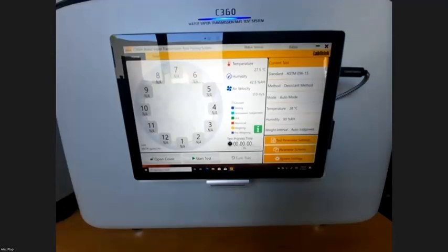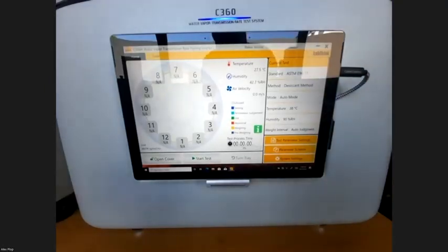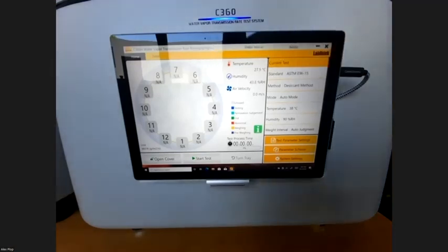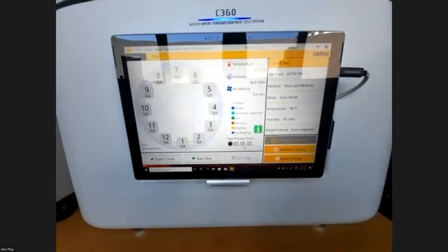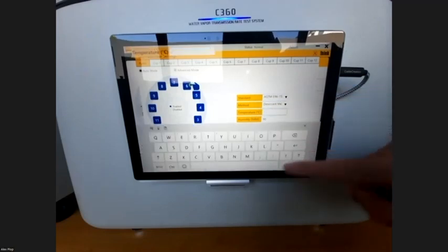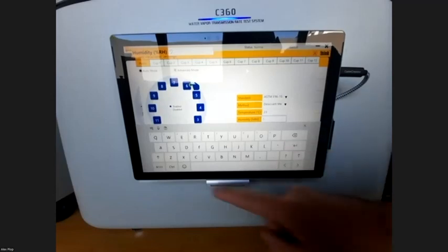On the right side of the screen, I can see information of the current test that I'm using. The standard that I'm using, in this case, is the ASTM E96. We have selected the desiccant method, the test temperature that is 38 degrees Celsius, and the humidity 90% relative humidity. And as I was telling you, after I install the samples and the cups, I need to come to this parameter. From here, I have the freedom to select whatever standard I want, with desiccant or water method, and to input whatever temperature and relative humidity I want. Based on my selection, the test will perform this or not.